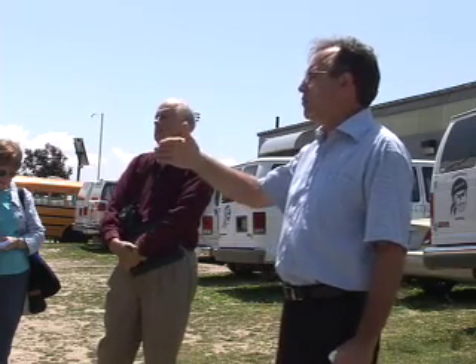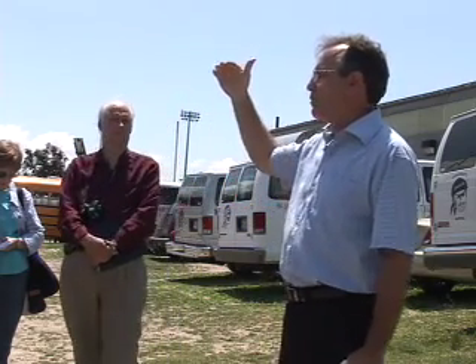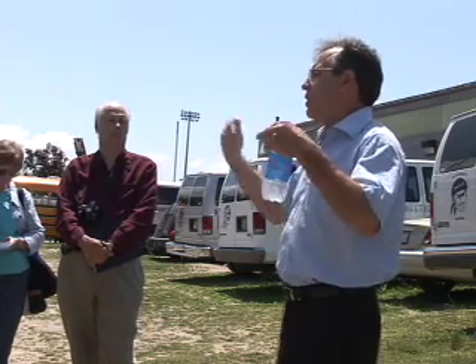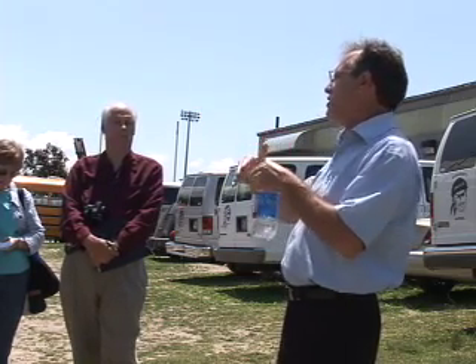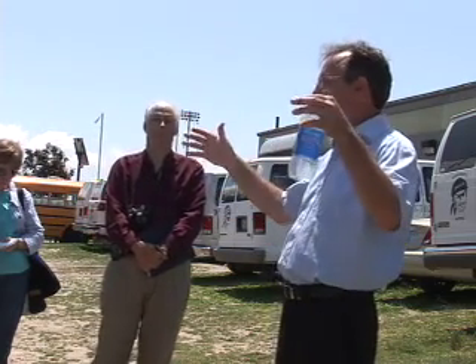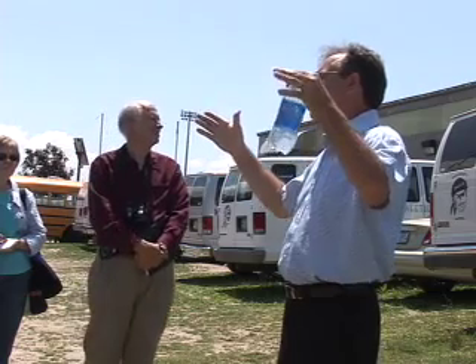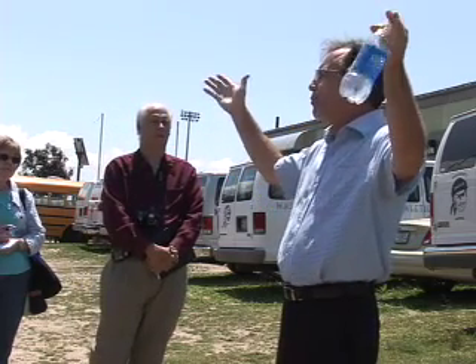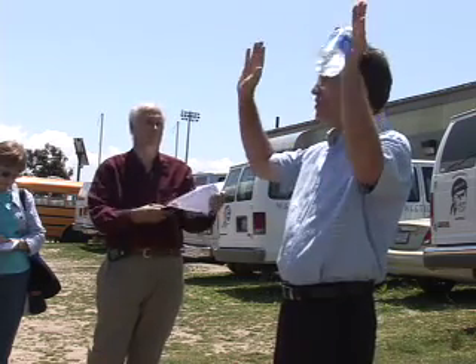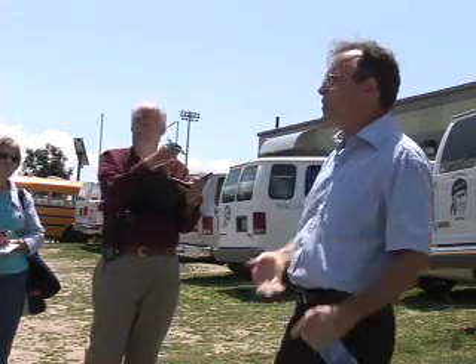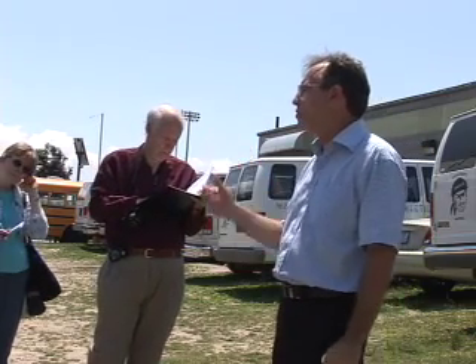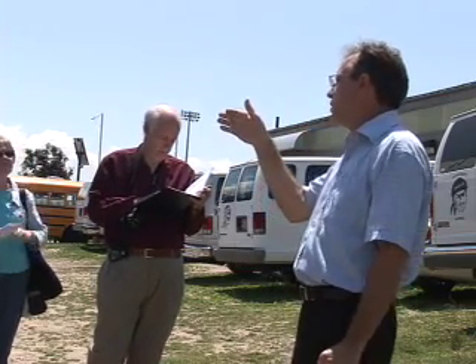From 33 mile an hour winds up to 55, that's more than we need. And there's actually a 10% swing there. It can go 650 plus 10%. The electronic controls allow that. There's resistors up there to bleed off energy. But anyways, up to that 50 miles an hour, it's starting to pitch the blades, dump energy, that type of thing. At 55, when it sees 55 mile an hour winds for 100 seconds, it shuts it down. It just pitches those blades back to zero. With a few revolutions, it'll just sit there and coast. Always the control system keeping it into the wind.